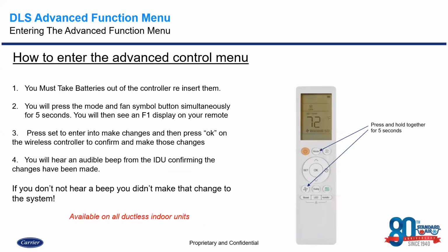And then finally, the advanced control menu. So why do we care about getting to the advanced control menu? Well, there's a bunch of different features that we can essentially customize this indoor unit for depending on the application. For example, we can shut fan speeds off after set point. We can program offsets on temperature sensors in a negative or positive fashion depending on if the unit's overheating or underheating, overcooling or undercooling. Okay, so what we're going to do is just like we did on the other wireless remote controller, aside from the buttons that we're going to press.